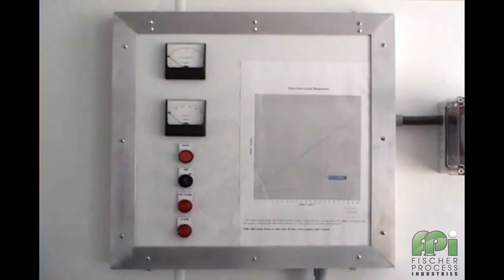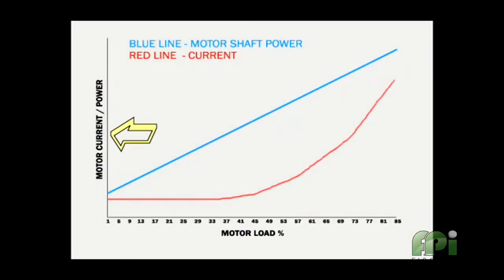This graph demonstrates the fundamental differences between the abilities of a current monitoring situation and that of the M20 shaft power monitor. This graph shows motor current and power on the vertical axis and motor load on the horizontal axis. The red line shows what happens to the current as load increases. Note how it remains virtually unchanged until the motor load reaches approximately 60 to 70% of the motor's rated power.